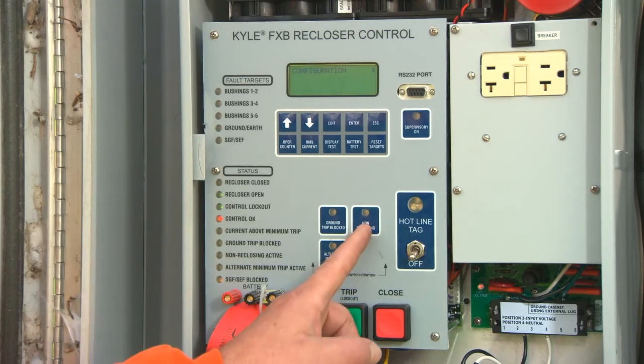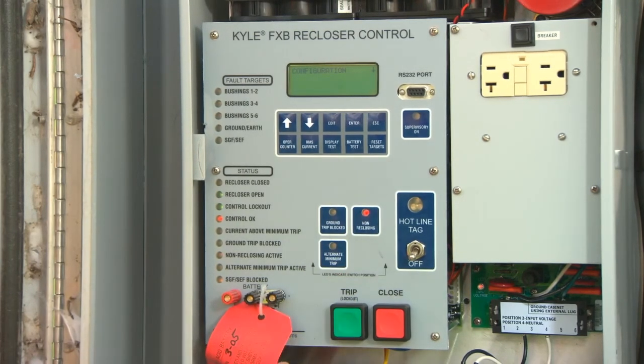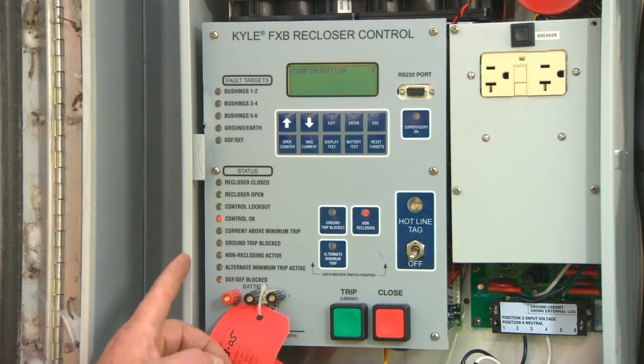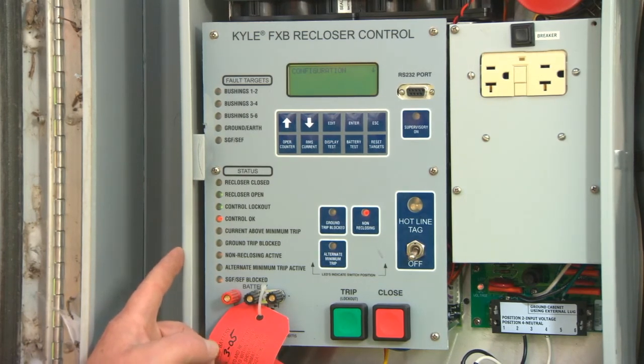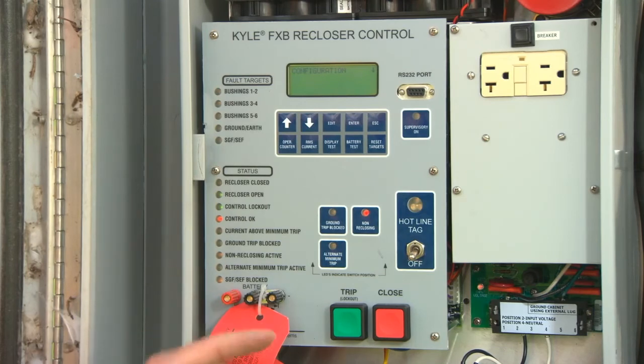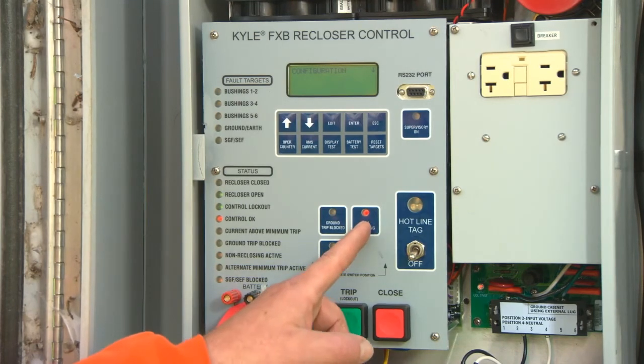Pressing the non-reclosing button will cause its LED to turn red and the non-reclosing active LED on the left side to turn amber. Regardless of its current state, there will be only one shot until lockout. Pressing it again will return to the normal multi-shot reclose.